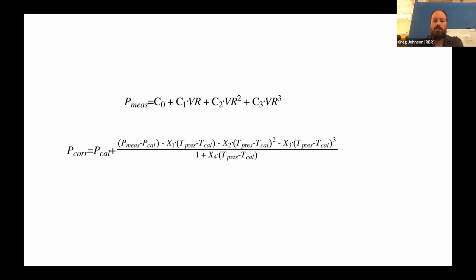And so we use those 2 tanks in order to exercise the instrument from 0 to full scale at 2 different temperatures. So one is the nominal room temperature, 20, 23 degrees Celsius for people who aren't bilingual. And one is our cold tank, which is usually 2 or 3 degrees. We also then take a measurement of the pressure sensor across the 0 pressure line, or let's say the atmospheric line, 10 dbar, over the full range of temperatures from -5 to 35. So we're in effect building up a 3-sided rectangle that we're able then to interpolate across the middle of.